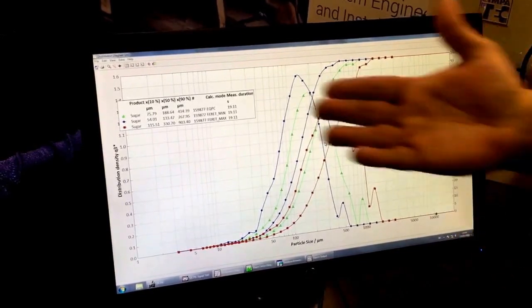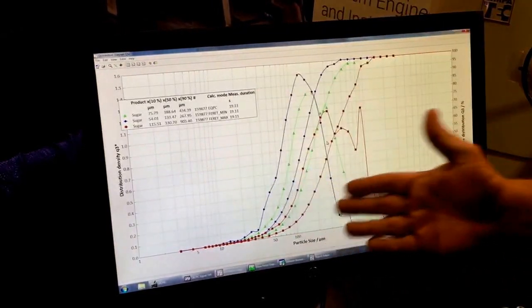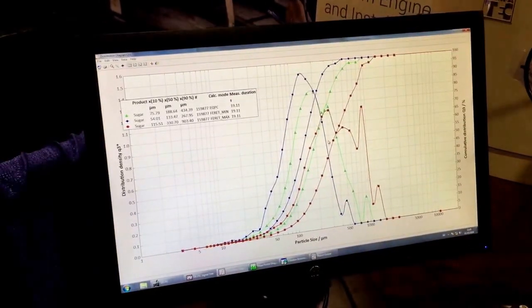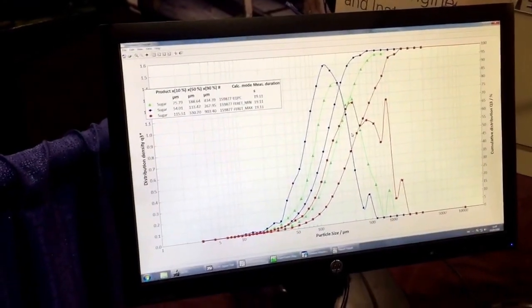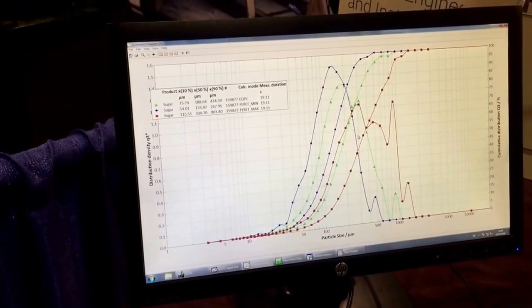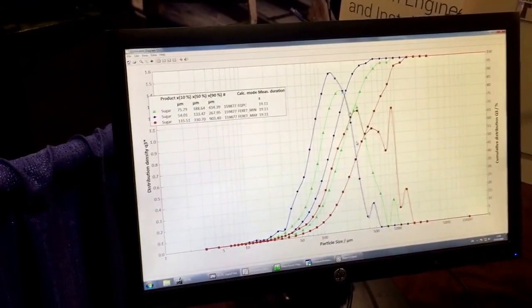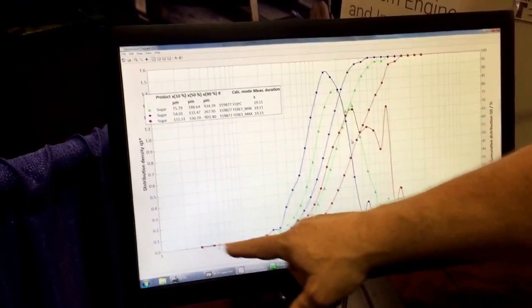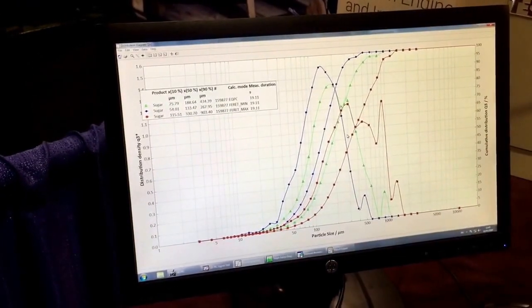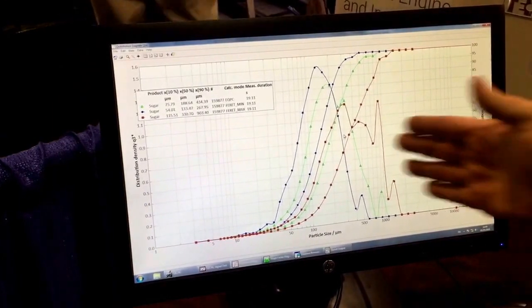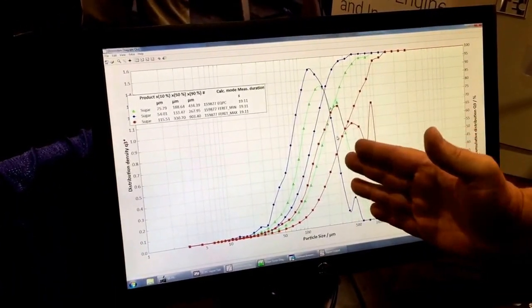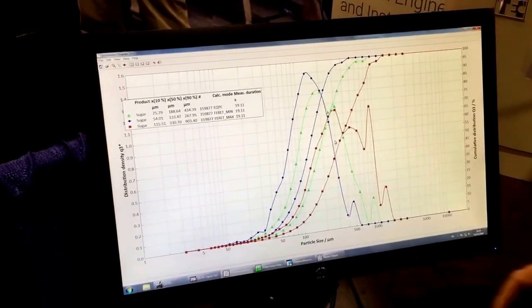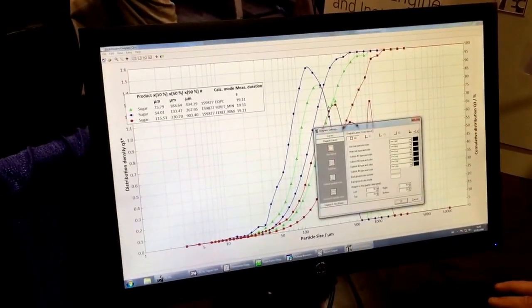So the big guys weigh more than the small guys or get more attention than the small guys. But I could also do a number-based distribution if I wanted to, where a five micron particle is equal to a one millimeter particle. Here you say, well there aren't any particles down there, but there are. Because you have such large particles, it's mass-weighted or volume-based weighted, but I can change that if I wanted to.